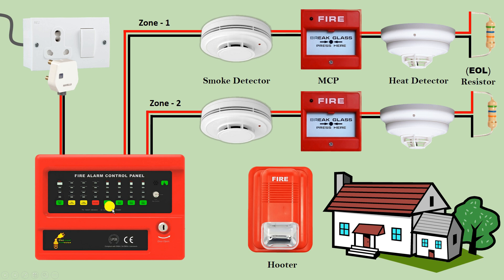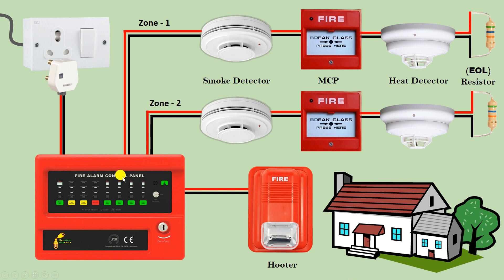In the fire control panel there are also two terminals for hooter connection. Connect wires from those terminals to the hooter. At the back of the hooter there are two terminals — connect positive and negative power supply there. If you have more hooters, connect them in parallel. After doing all these connections, if your house catches fire, the fire control panel will generate an alarm and you will be able to know there is a fire.